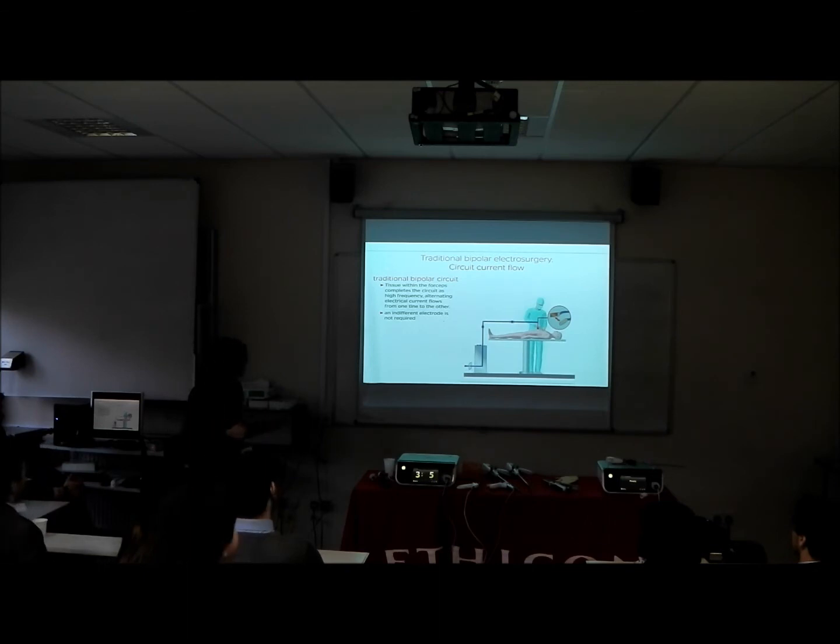So in the previous one, once the current entered the patient's body, the patient formed part of the circuit, and the current went through the whole patient's body. But in the bipolar one, it does not.